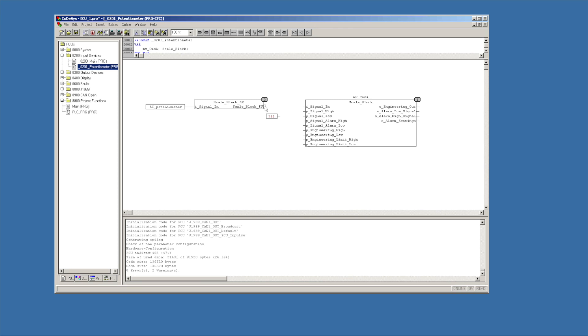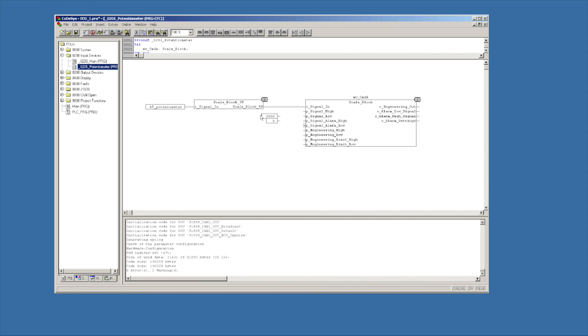I'm going to take another input down here. I need to say, I've got a signal coming in from the potentiometer, this zero to 5,000 value. It's coming to my signal in. Now what could the signal high be? Well, the high value right now is 5,000 millivolts. The low value will be zero.